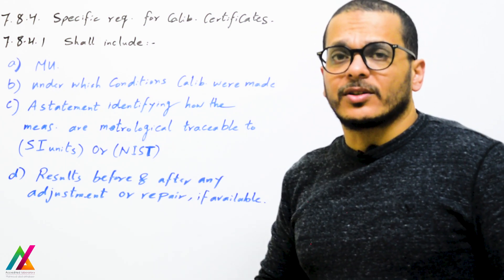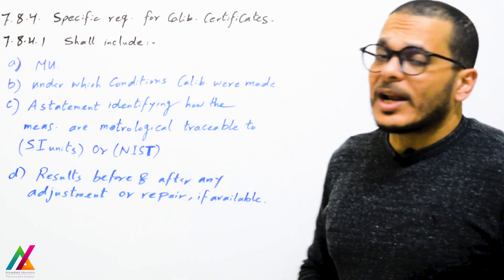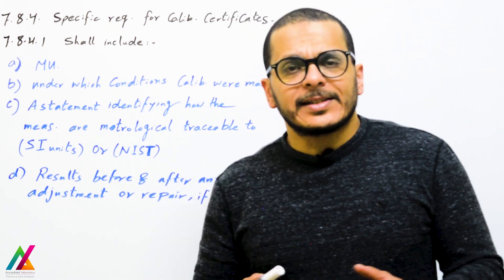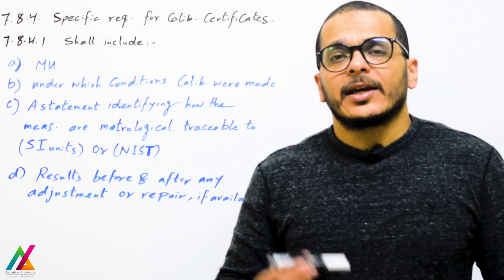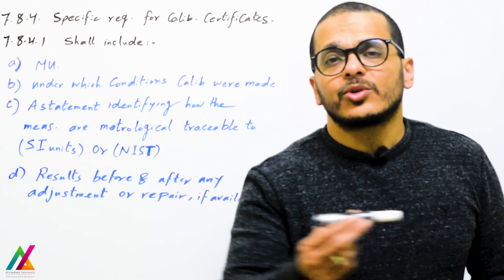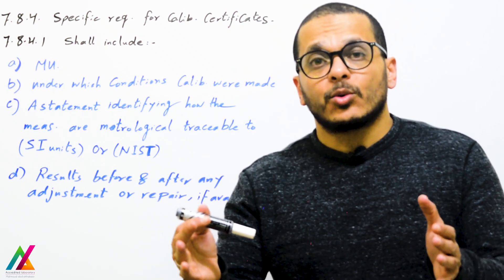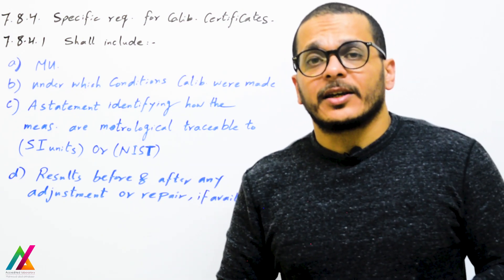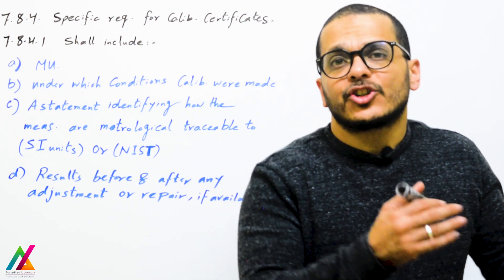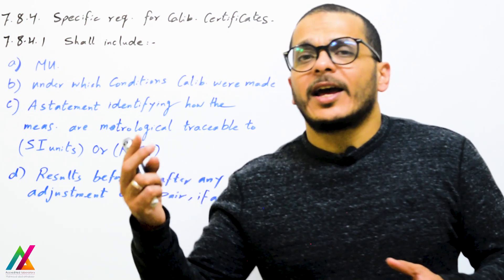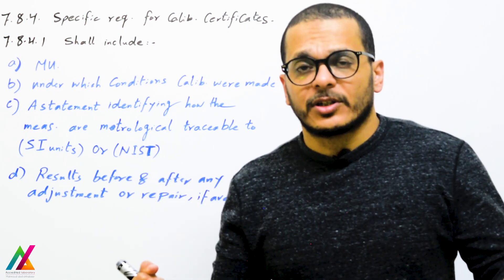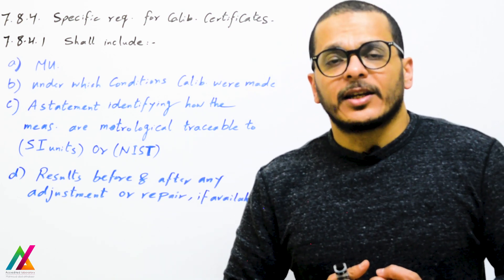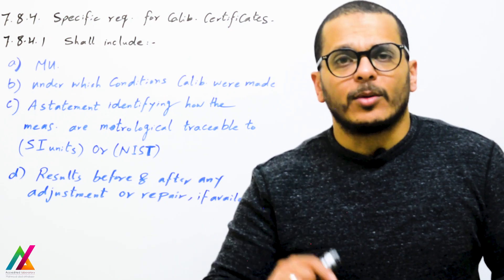Also in the calibration certificate: results before and after any adjustment or repair of the equipment, if available. For example, if calibration was performed and failed, then the equipment was fixed or repaired, there will be results before and after the repair, and after the repair the calibration passes. These before-and-after results shall be included in the calibration certificate if available.